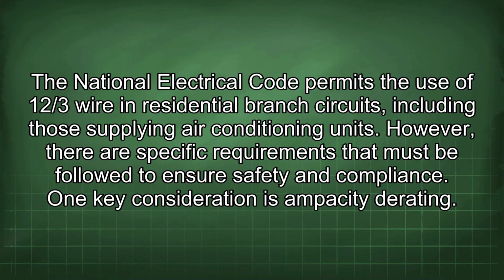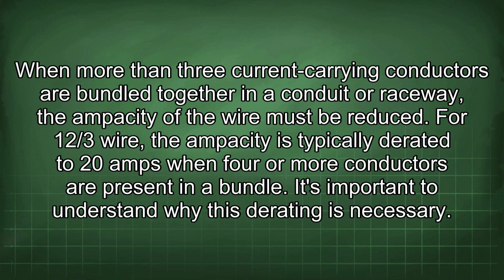The National Electrical Code permits the use of 12/3 wire in residential branch circuits, including those supplying air conditioning units. However, there are specific requirements that must be followed to ensure safety and compliance. One key consideration is ampacity derating. When more than 3 current-carrying conductors are bundled together in a conduit or raceway, the ampacity of the wire must be reduced. For 12/3 wire, the ampacity is typically derated to 20 amps when 4 or more conductors are present in a bundle.